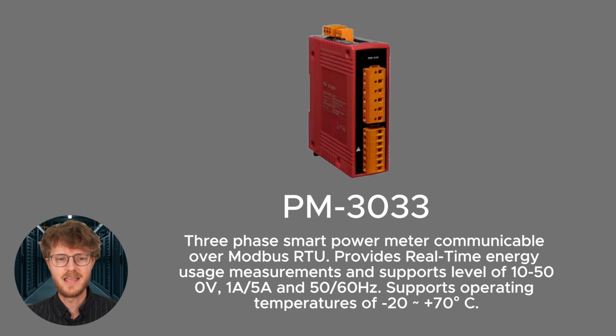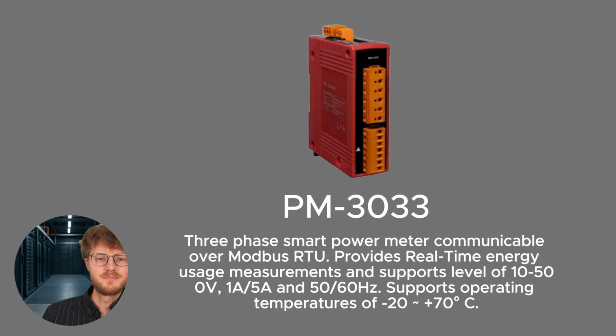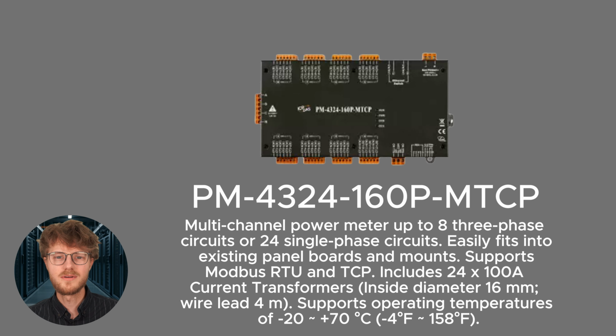So to put it even more simply, if you need basic kilowatt and amperage readings and you own a legacy system, you could use this PM meter along with Modbus RTU. If you need more advanced analytics and you own a modern system, you could use this PM meter along with Modbus TCP. Great, so now we're able to not only catch the environmental issues like temperature, humidity, and airflow with our DL logger, but we also have circuit level visibility, so we know exactly how much energy the chillers, pumps, and fans are consuming. Now lastly, in the next video, we'll be going over how to pull it all together with a WISE controller and finally have complete control and oversight into what's actually going on in your data center.